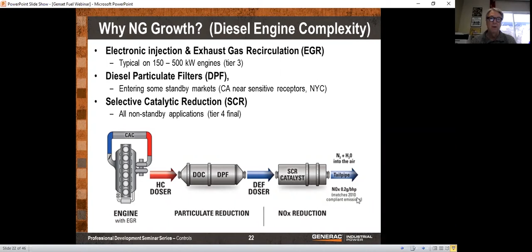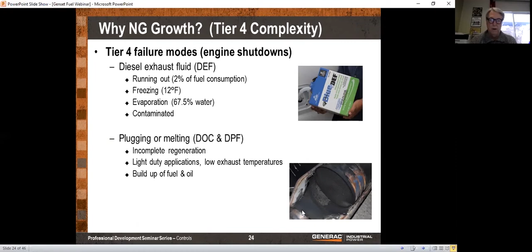These things are all used commonly in prime power, but when you use them on standby power, they cause a lot of problems. This is some of the sensors used for post-treatment, which drive up the cost. Look at this particulate filter in the lower right — it just gets full of soot and stops working. If you run your diesel generator at higher loads for long periods, that soot will combust and stay clean, but with a standby generator you have to clean it out by hand. So all these things are creating more and more problems for diesel.